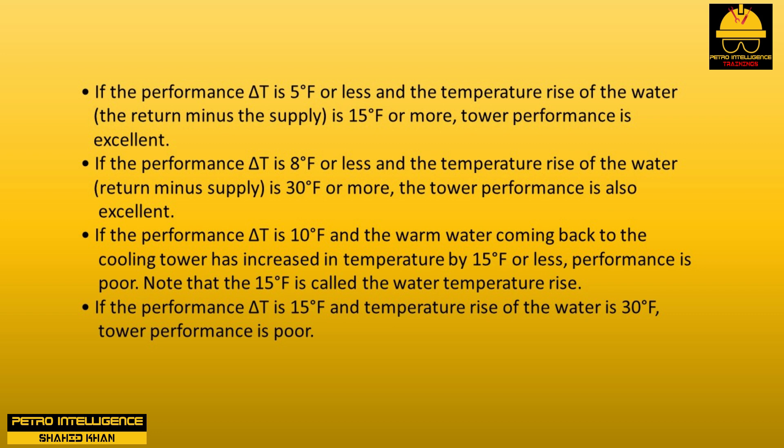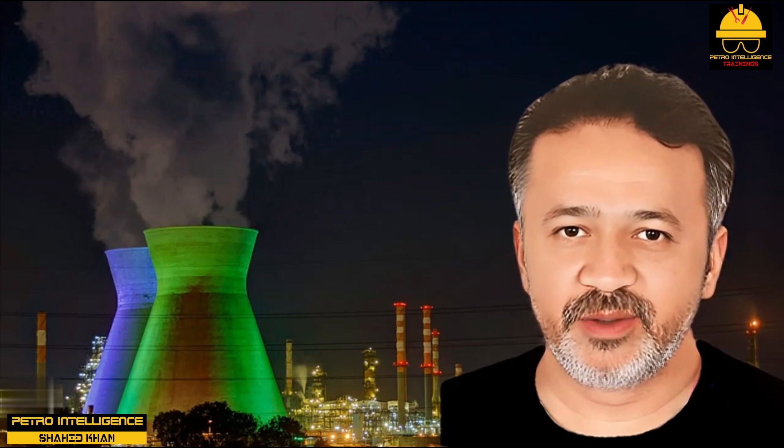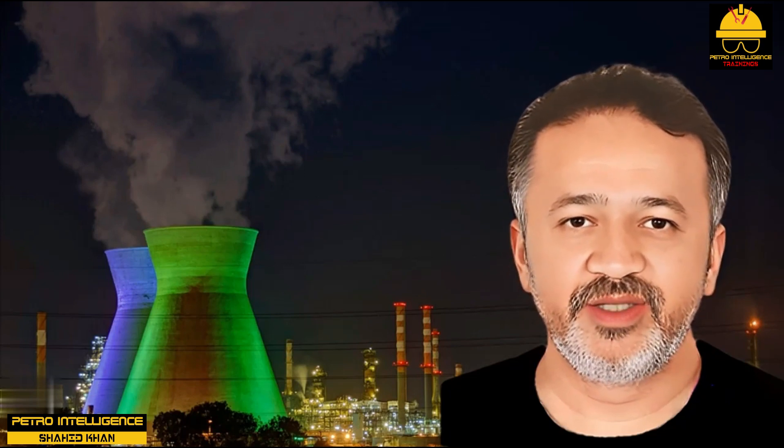The 15°F difference is called the water temperature rise. If the performance delta T is 15°F and the temperature rise is 30°F, tower performance is poor. In older induced draft wooden cooling towers, common problems include broken wooden slates and plugged water distribution holes or large holes broken into the deck. Water should not overflow around the outside of the tower. On some cooling towers, fans are driven by belts which can slip, or the fan blade pitch is set too low — below 15 degrees, with a maximum of 23 degrees.